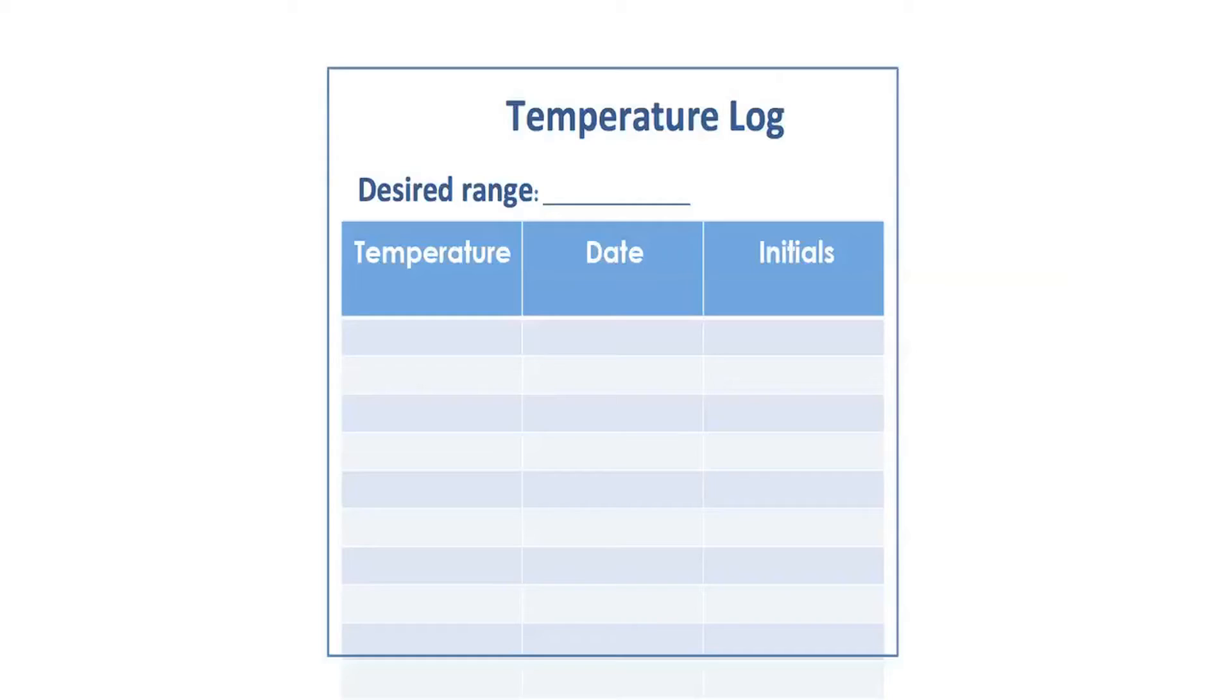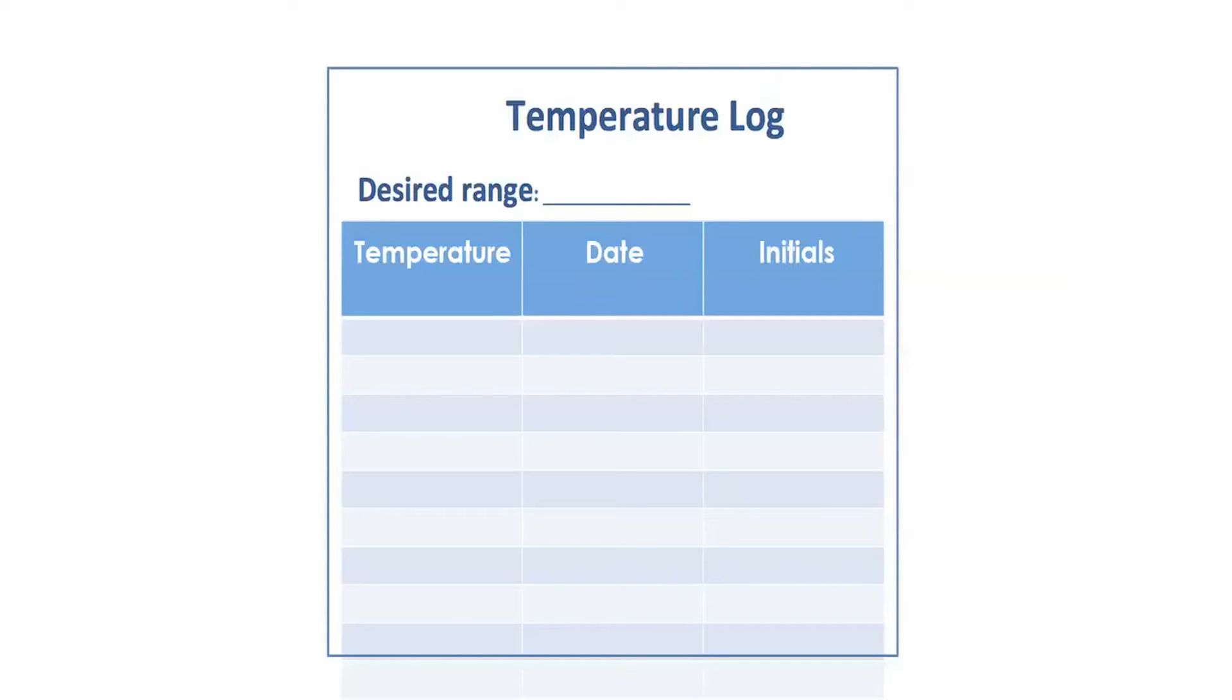In the majority of labs that I have seen, temperature tracking, if done manually, is done on a log, which means temperature is recorded in one column, followed by the date in another column, and followed by the initials of the individual who made that observation.